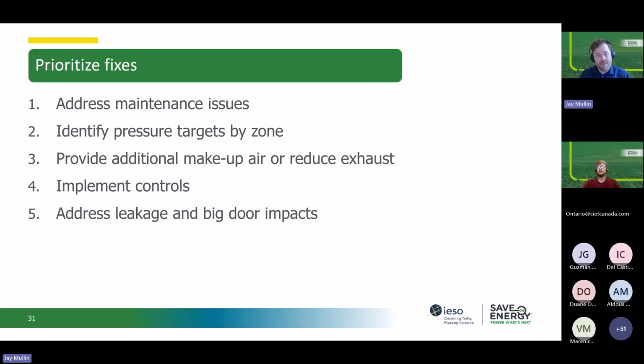The next priority for the fixes is implementing controls. An example of this is interlocks between exhaust and makeup air units, connecting those to processes so that during operation they're locked together. If exhaust comes on, equivalent makeup air unit capacity comes online, and they turn off when they're not needed. Controls can also control fan speed, dampers, and relief based on the building pressure set point. So in a BAS, you may say we don't want to exceed a +5 Pascal differential, and it'll bring in more air if there's more exhaust, or control the input and output of the air if that threshold is exceeded.